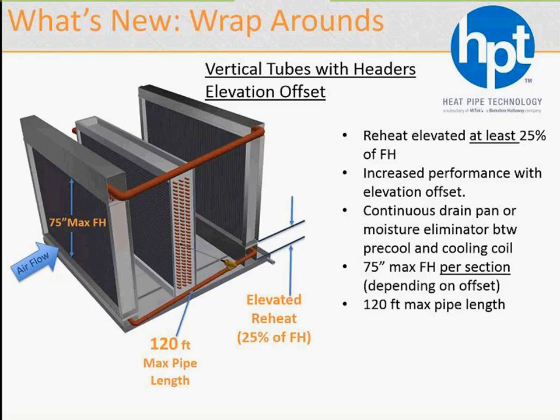The distance increases because of this slope from 60 to 120. You will never need that long for the pre-cool reheat, but it's there should it be needed. Now, the uniformity of the temperature across the face of the reheat is pretty good for this particular product, so no air blender is required. Now, if you don't have the continuous drain pan, a moisture eliminator would be needed as well. I didn't mention that earlier.